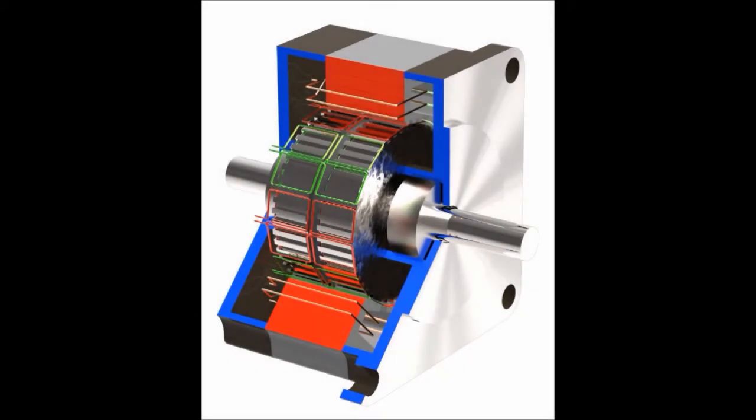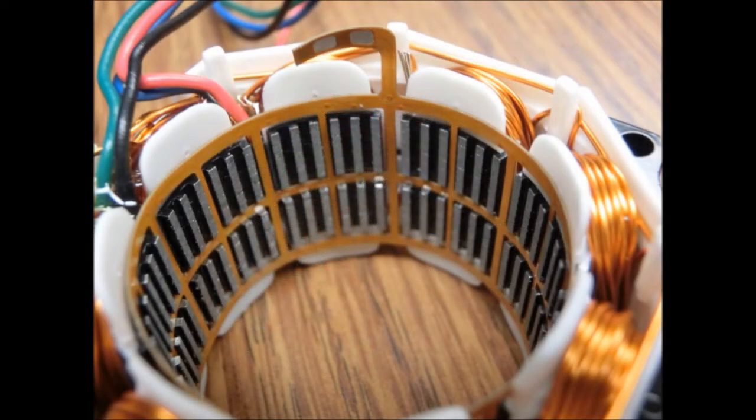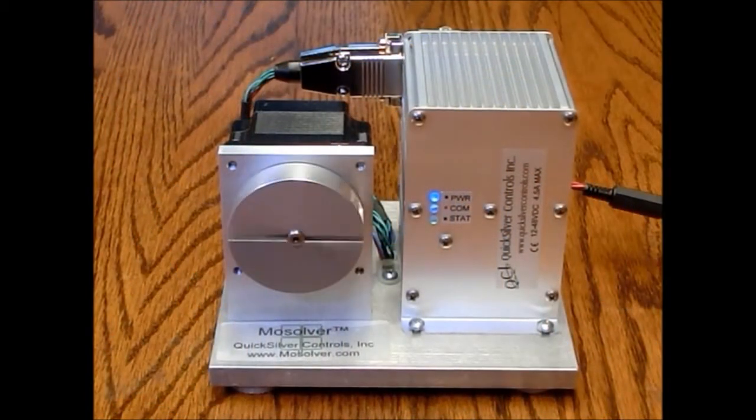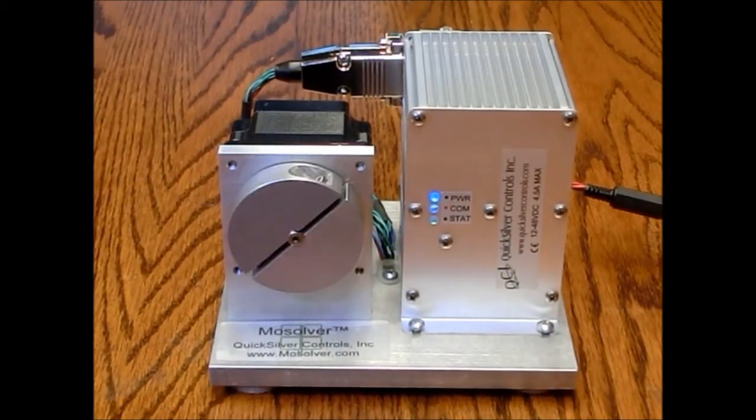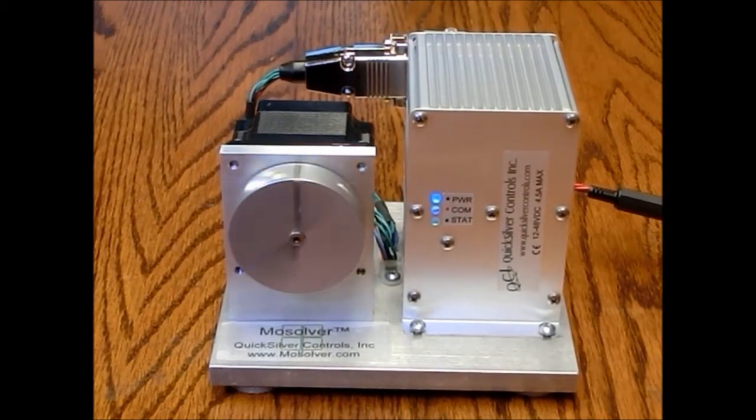The Mosolver is a combination motor and resolver built on the same magnetic structure. A sense coil has been added within the structure of the stator to sense a portion of the PWM signal. The coupling varies according to the position of the rotor. This produces 32,000 counts per revolution as well as commutation information providing for excellent motion control.